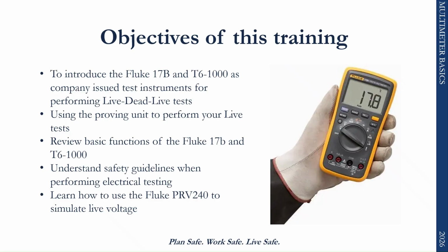Today's training is focused on a few main areas. First, we'll introduce the Fluke 17B digital multimeter and the Fluke T6-1000 electrical tester, which are the primary test instruments issued for use in the field. We'll also talk about the Fluke PRV240 proving unit, which is used to verify that your meter is working properly before and after testing. Another important part of this training is reviewing the live-dead-live testing procedure, which is the standard method used to confirm absence of voltage during lockout-tagout. Finally, we'll cover some general safety guidelines when using electrical testing equipment.